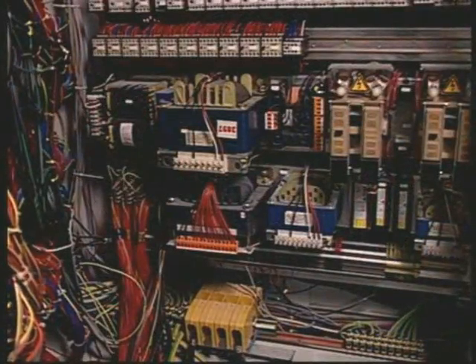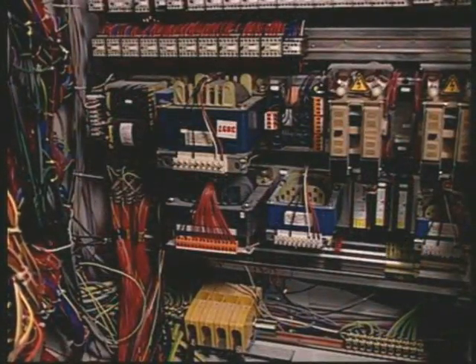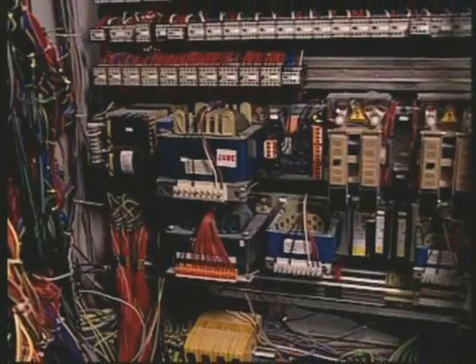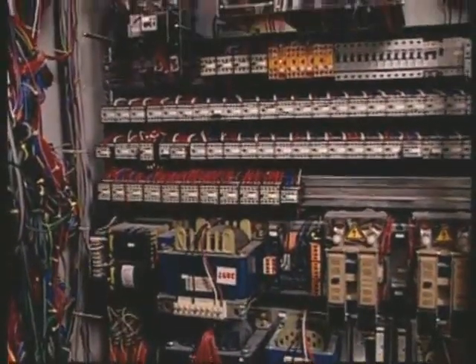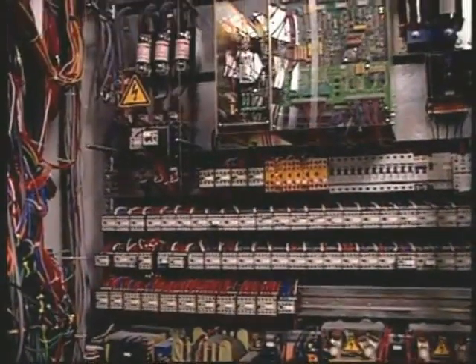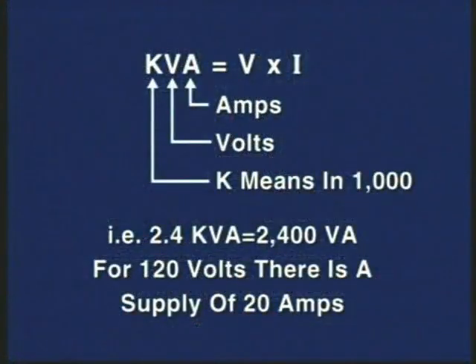Although overloading the transformer seldom occurs when a control system is first designed, we need to keep track of the devices we add to the circuit. For example, during an expansion of a system. If our 120 volts transformer is rated at 2.4 kVA, it is capable of delivering 20 amps without exceeding its capacity. If the sum of all the devices on at the same time exceeds 20 amps, we will see faults in the system.